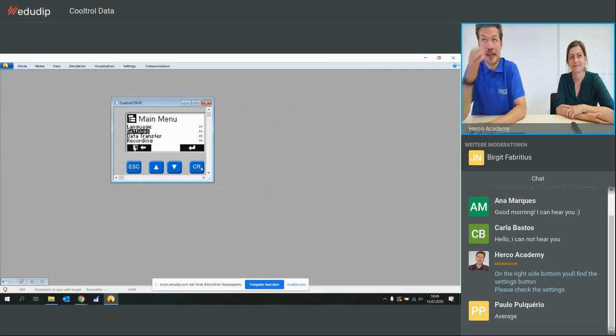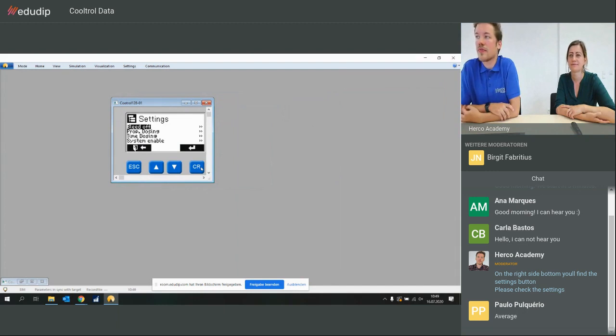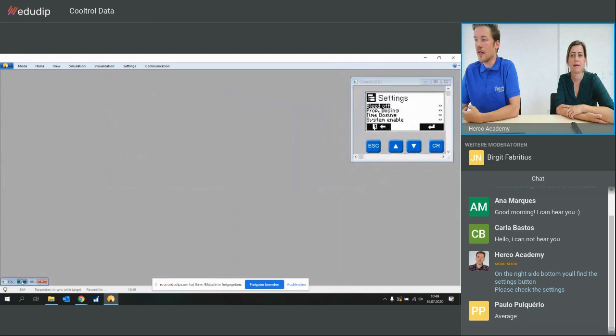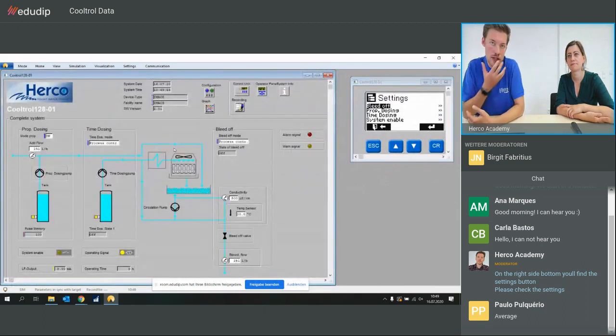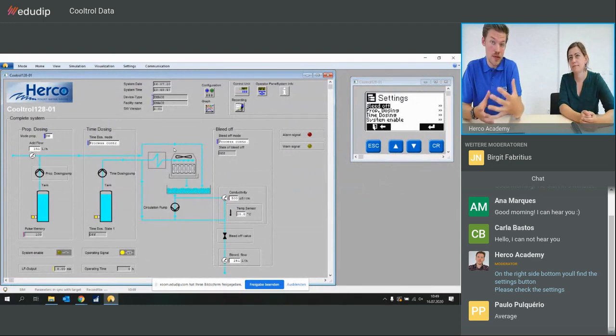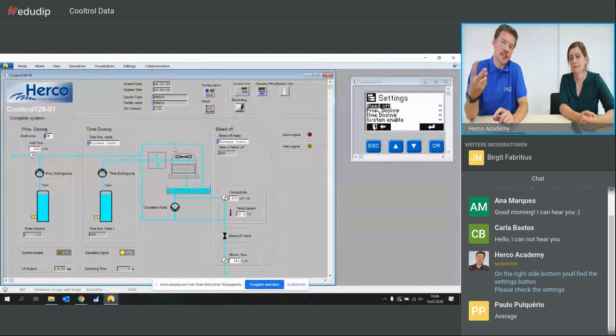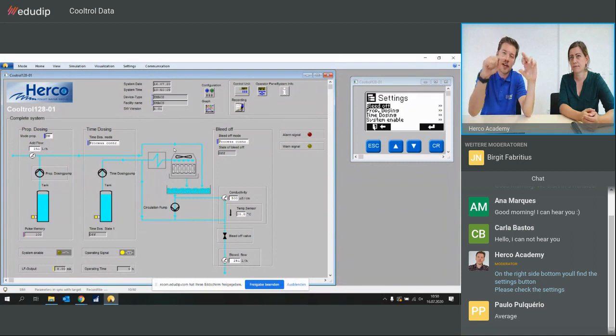All right, so inside the settings, we have the information for all the different. We have a question. Can we write information from the dosing systems? The chemical is going out, but the alarm comes only when it's empty, but earlier the level is low. Do you mean maybe not that it's completely empty, but like a pre-alarm? You know that on the pumps we are using, those are mainly Grundfos dosing pumps, and they always have two levels. It depends on the dosing pump you're using from Grundfos. They mostly have two levels, so there's a pre-alarm and then the alarm.